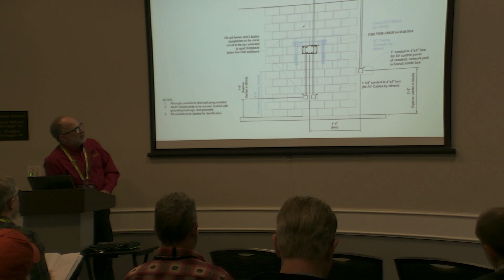So why did you pick 4 11/16ths instead of a 4-inch box? The 4 11/16 boxes have bigger knockouts for conduits. You can get 1.25 inch, 1.5 inch in a 4 11/16 by 4 11/16 box, but you cannot get them in a 4 by 4 inch box. Typically a 4 by 4 inch box is limited to 1 inch conduit max.